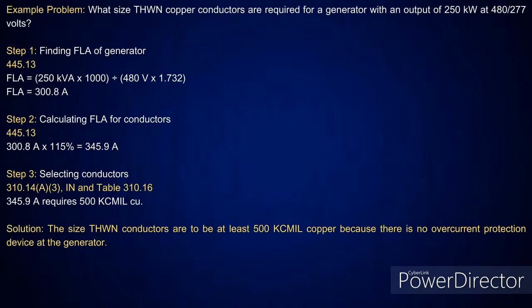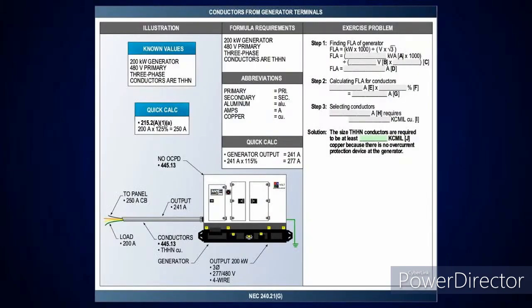That's simple. Okay? And a lot of people think this is hard, but if you look, I'm dealing with transformers and generators. What did I have to do? I needed to know the kVA of the transformer or generator, then the voltage, divided into it to get my amperage. That's it, in order to size my conductors.